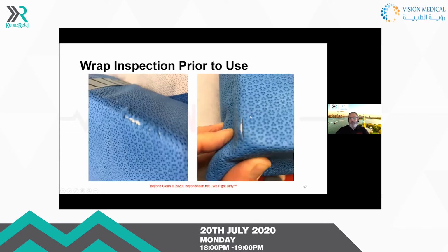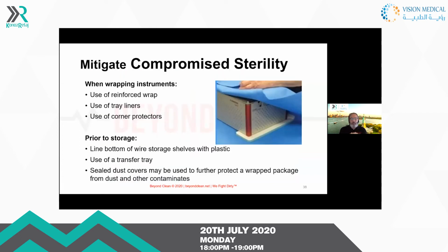Again, as you perform your audits, you want to make sure that if you have blue wraps on the shelf, they are maintaining the integrity of sterilization. When wrapping instruments, you want to make sure you use reinforced wraps. They have tray liners out there now that you can use. They have corner protectors that will protect your instruments. You want to make sure that your shelving is protected so that you do not damage these devices as you place them onto the wrapper.